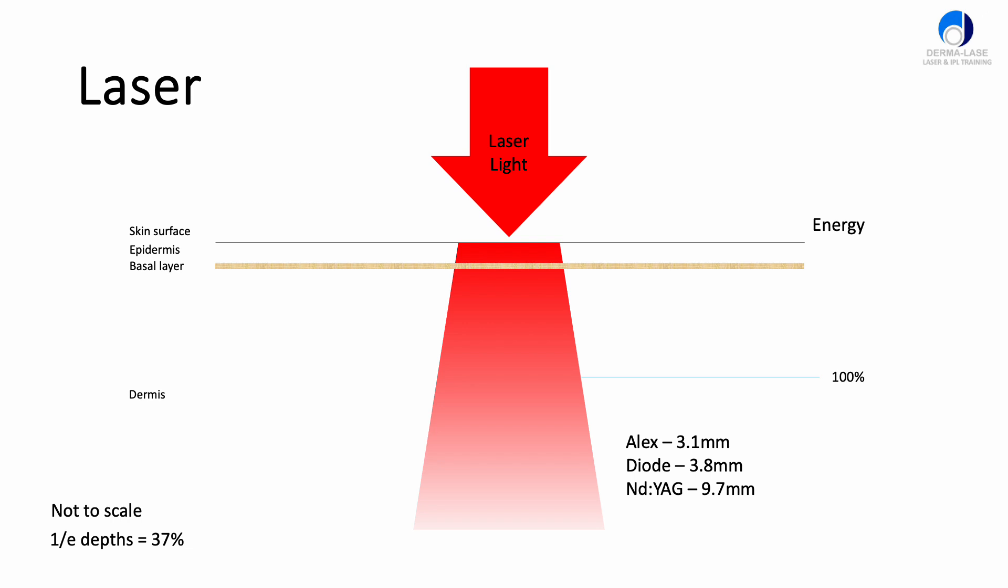The alexandrite laser which is a 755 nanometer wavelength penetrates about 3.1 millimeters. The diode laser that we use typically for hair removal, usually 808 or 810 nanometers, can penetrate a little bit further to about 3.8 millimeters. But the ND YAG laser with the 1064 nanometer wavelength penetrates the furthest, 9.7 millimeters, mostly because its absorption is so low in the constituents in the skin and its scattering is very much forward.